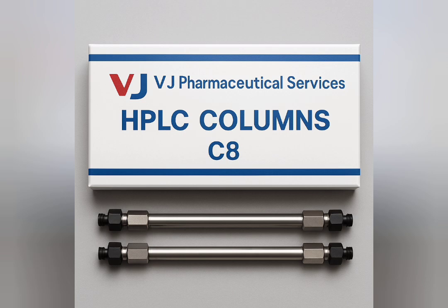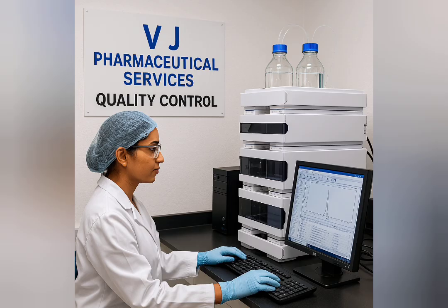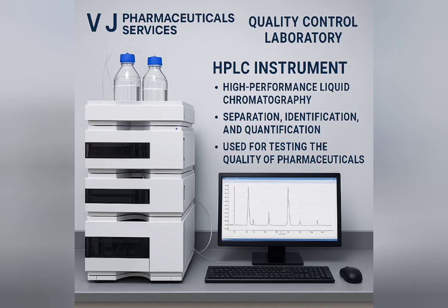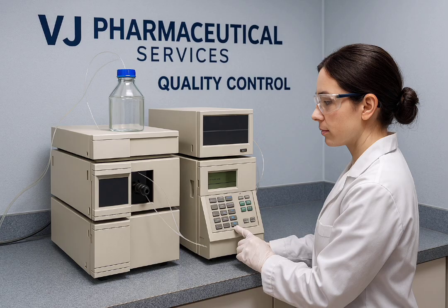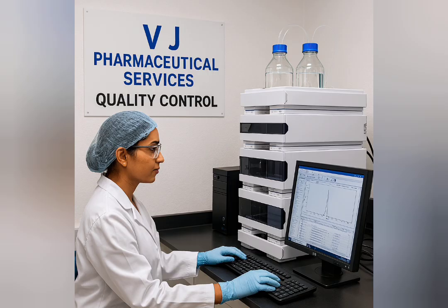Isocratic versus gradient elution modes. Isocratic elution: a single composition of solvents is used for the duration of the separation. Later eluting peaks are broader than earlier eluting peaks because of dispersion. Steps must be taken to periodically flush the column at higher solvent strength to clean it of intractable materials that build up from sample injections.